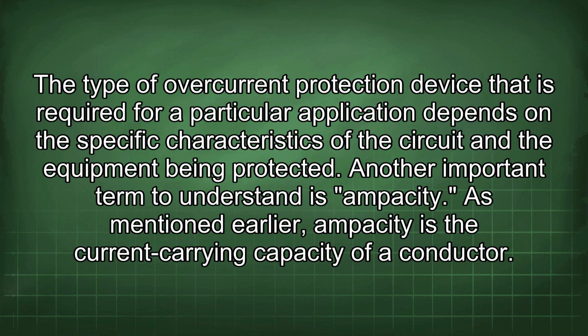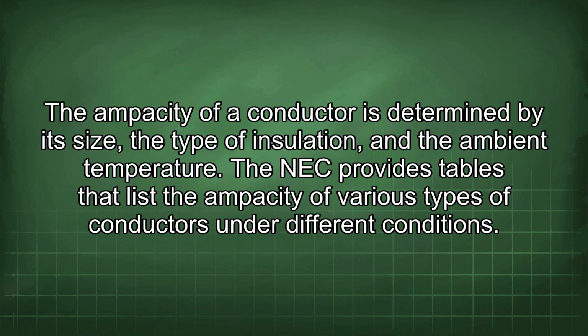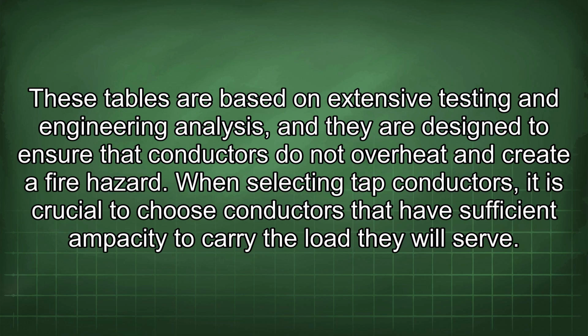Another important term to understand is ampacity. As mentioned earlier, ampacity is the current carrying capacity of a conductor. The ampacity of a conductor is determined by its size, the type of insulation, and the ambient temperature. The NEC provides tables that list the ampacity of various types of conductors under different conditions. These tables are based on extensive testing and engineering analysis, and they are designed to ensure that conductors do not overheat and create a fire hazard.